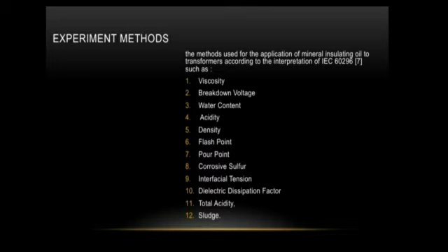Experiment methods. The methods used for the application of mineral insulating oil to transformers, according to the interpretation of IEC 60296, are as follows. Number 1, viscosity. Viscosity is important in controlling heat dissipation. Number 2, breakdown voltage. Breakdown voltage is a measure of the ability of insulating oil to withstand electrical stress and is very important for safe operation of electrical equipment.